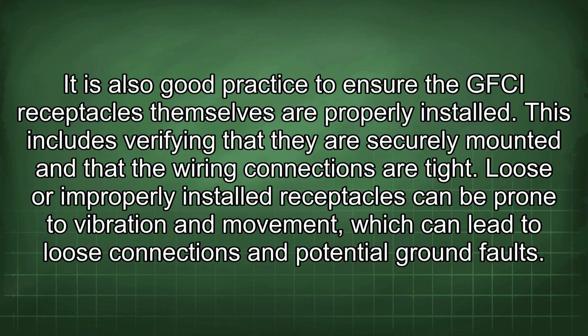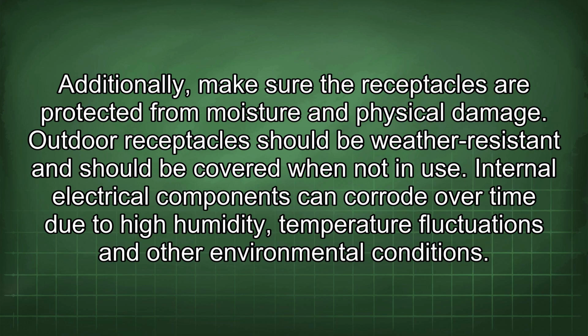It is also good practice to ensure the GFCI receptacles themselves are properly installed. This includes verifying that they are securely mounted and that the wiring connections are tight. Loose or improperly installed receptacles can be prone to vibration and movement, which can lead to loose connections and potential ground faults. Additionally, make sure the receptacles are protected from moisture and physical damage. Outdoor receptacles should be weather resistant and should be covered when not in use.